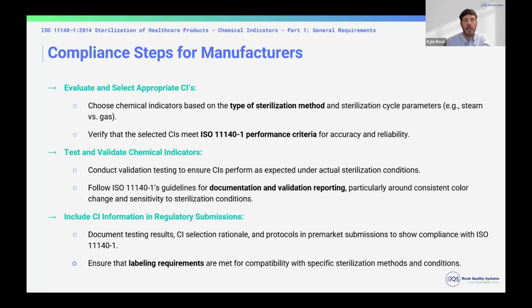Typically for companies that are ISO certified, there's a specific sterilization audit where they're just focusing on sterilization by a subject matter expert in sterilization. It's typically every 2 or 3 years, so this information will be covered directly in that special audit covering sterilization. So making sure that you have this information, if you're doing it internally, or if you're outsourcing sterilization, that you have this information from your sterilization vendor, and they're tracing this back to the manufacturers of these chemical indicators.